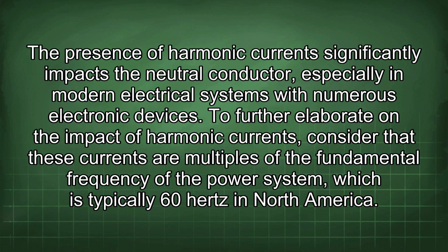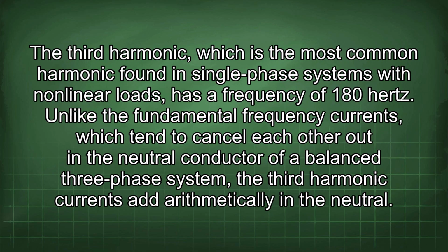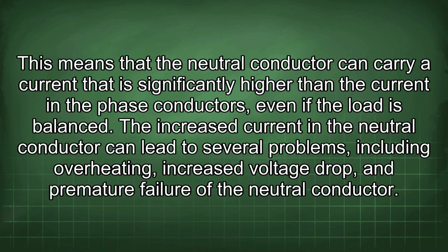To further elaborate on the impact of harmonic currents, consider that these currents are multiples of the fundamental frequency of the power system, which is typically 60 Hz in North America. The third harmonic, which is the most common harmonic found in single-phase systems with nonlinear loads, has a frequency of 180 Hz. Unlike the fundamental frequency currents, which tend to cancel each other out in the neutral conductor of a balanced three-phase system, the third harmonic currents add arithmetically in the neutral. This means that the neutral conductor can carry a current that is significantly higher than the current in the phase conductors, even if the load is balanced.